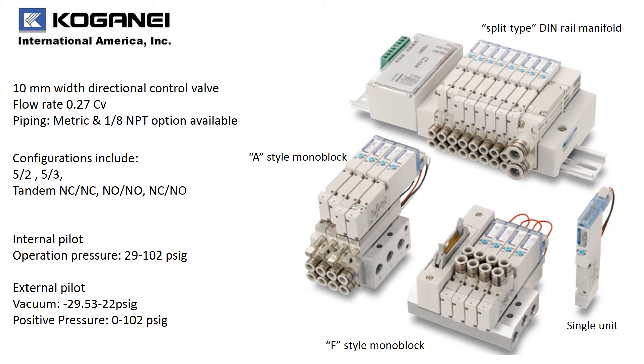Configurations include 5/2, 5/3, and tandem configurations. The internal pilot manifold will allow you to have an operation pressure of 29 up to 102 PSI. With the external pilot manifold, you can do vacuum at 29.53 inches of mercury up to 22 PSI, as well as positive pressure from 0 to 102 PSI.